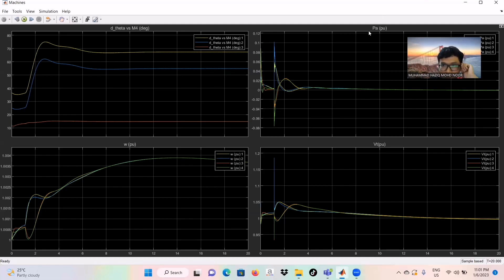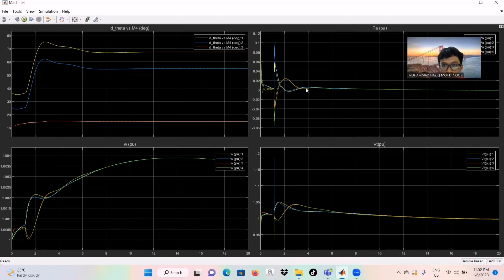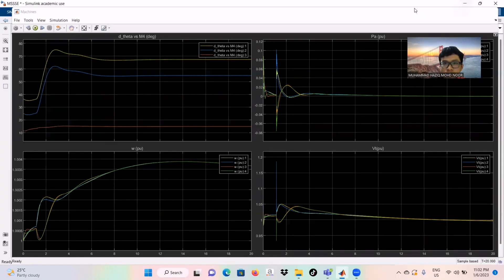For the electrical power consumed in per unit, generator machine 1 (blue and yellow) increases by about 0.12 per unit for one second, while generator machine 3 and 4 (green and red) become negative at -0.08 per unit. During 1.5 to 2 seconds, the temporary fault occurs and both machines are unstable. As soon as it reaches 4 seconds, both machines achieve stability and equilibrium. The voltage supply or total voltage per unit follows the same case as the electrical power consumed.